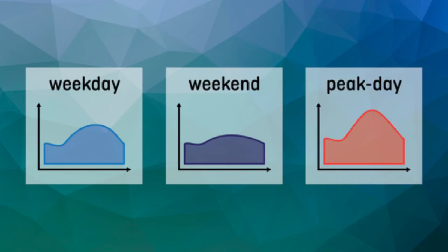This peak day type is intended to represent the 3 days each month where loads are highest. It's typically these days that will set electricity demand charges, which can comprise a significant fraction of monthly electricity costs, and can thus have a lot of influence over optimal system design. Users can add additional design day types to capture events like outages, demand response events, or critical peak pricing events, but in general, the variety of days is reduced significantly compared to a full 365-day design period.